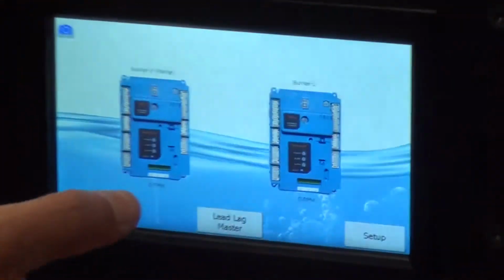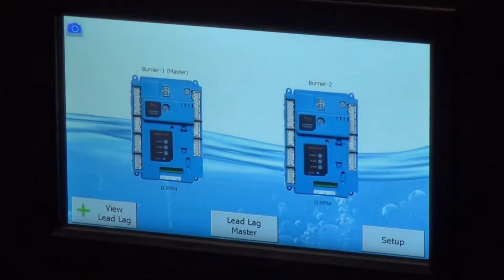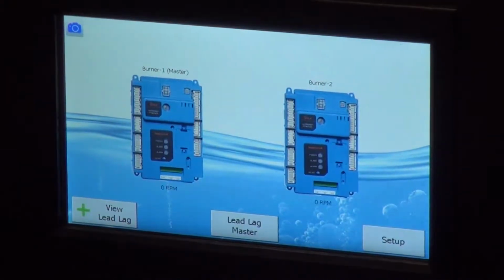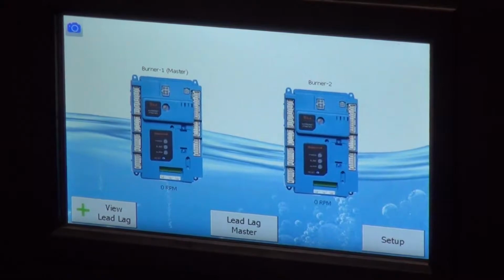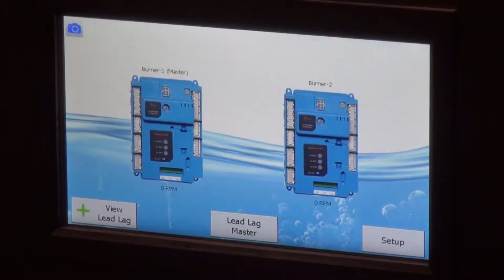Okay, other things you can do on here is in a differential setting, meaning when do we want this thing to come on. Let's say that's set at 145. Our boiler's set at 150. This thing's going to be set at 145 because it's relaying that temperature of that tank. The differential of the units is going to be, okay, when do we want that heater to kick on? We're not going to want it to kick on instantly when this thing drops underneath 145, or else we're going to have short cycling occurring within the boilers. So we set what's called a set point differential on there.